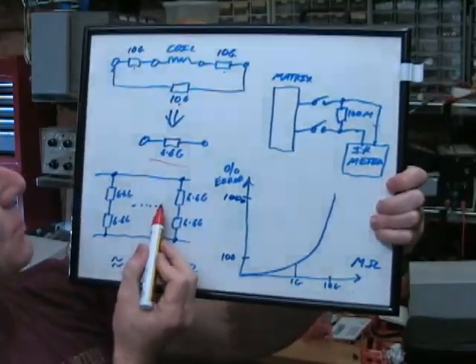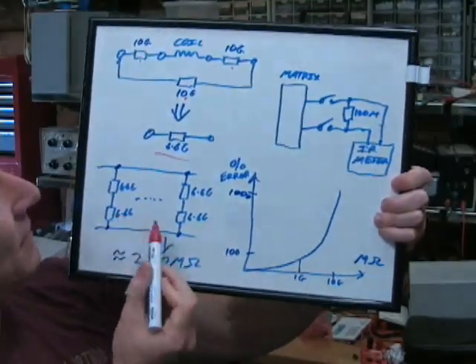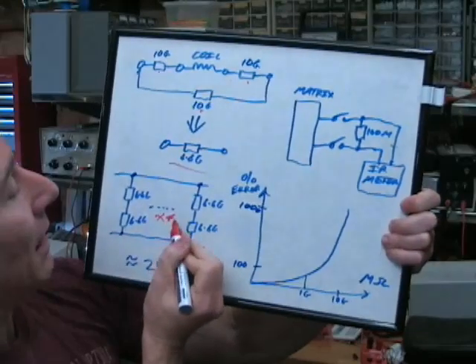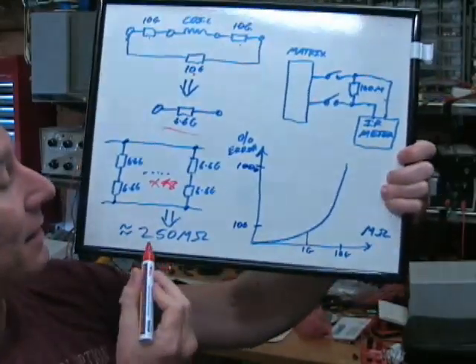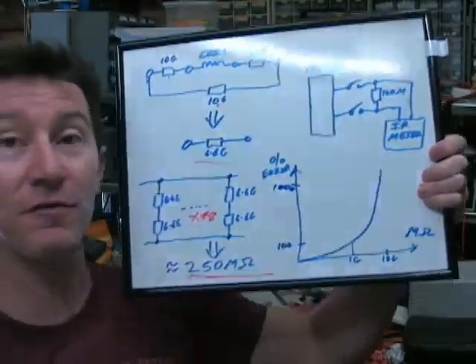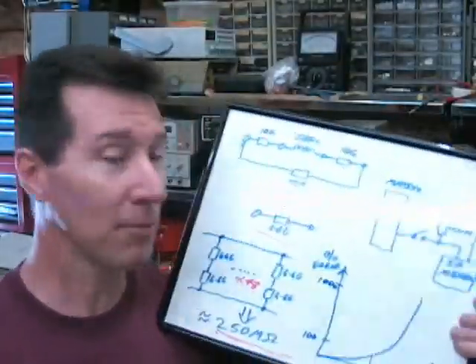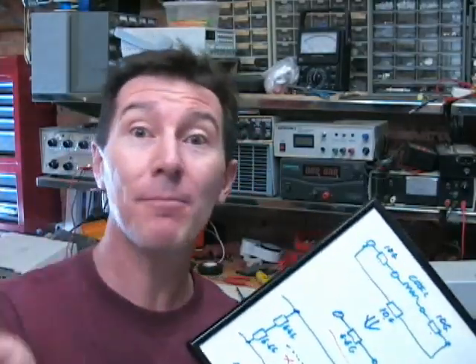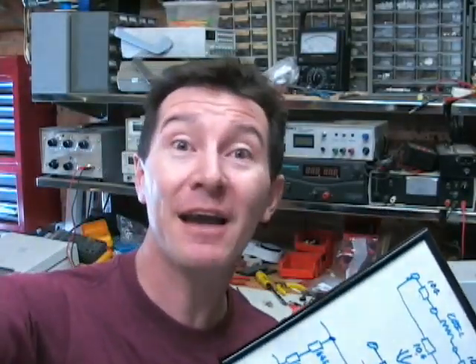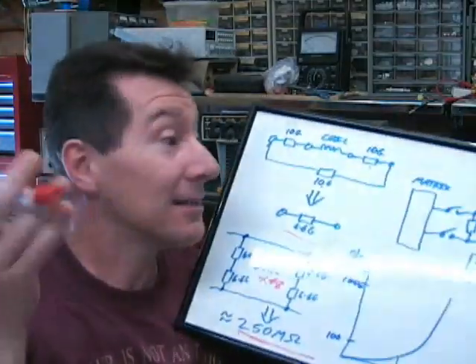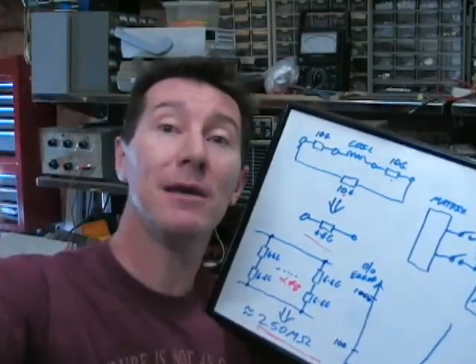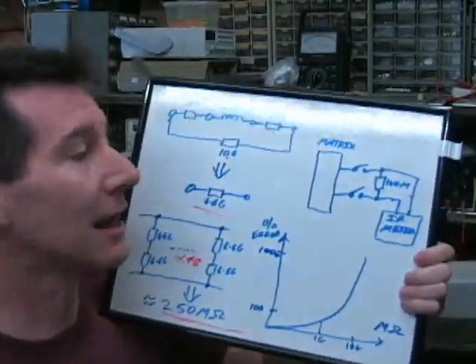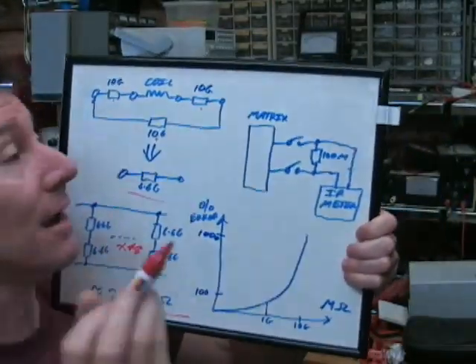But when you put it into a relay matrix like this, they're effectively in series and you might have 48 of them in series and parallel combination. That'll give you a total value, it comes down to 250 Meg. You might think that's still not too bad. Yeah, but it varies with temperature, time, someone farting across the other side of the factory. It just varies all over the shop. It's terrible. It wanders over the space of minutes and seconds. It's pretty horrible.